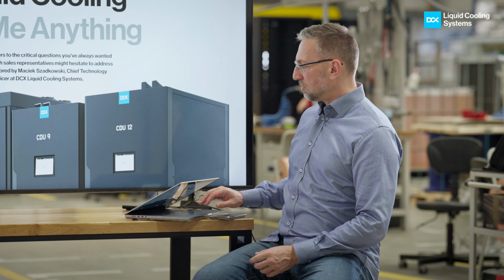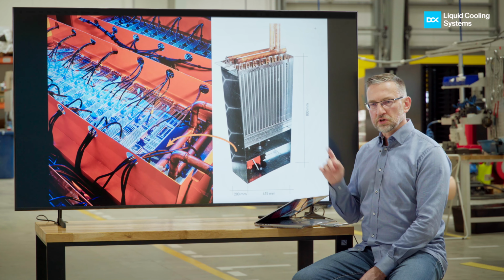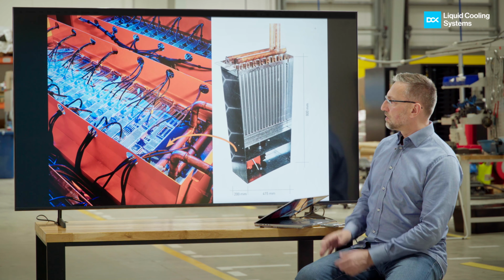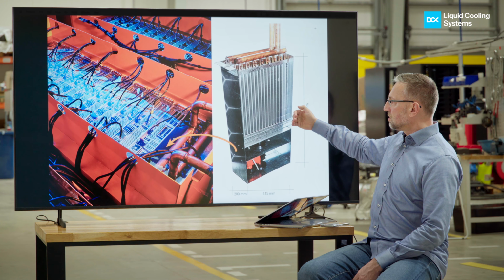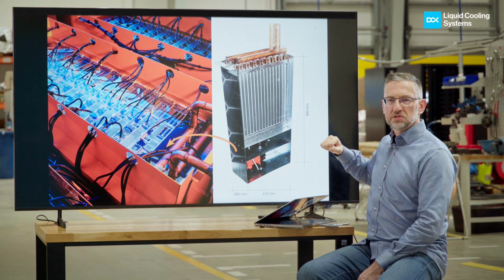But with immersion cooling, I know there are some companies which say they have something called a CDU inside of the tanks, but that doesn't make any sense. It's not a CDU. It's a heat exchanger, and that's one of the companies. For some time they were just using immersion cooling for their own purpose. Recently they also offer those very simple tanks, and they invented and patented the concept of having a more or less standard heat exchanger, which is also used for air cooling, and the pump located at the bottom. That heat exchanger circulates the coolant through it by means of that pump, and it's fully immersed in the tank. That was the patented solution.